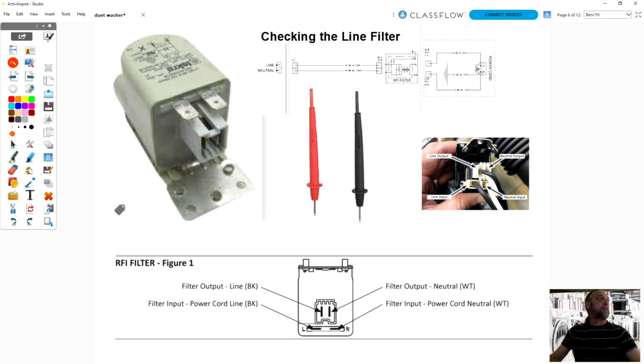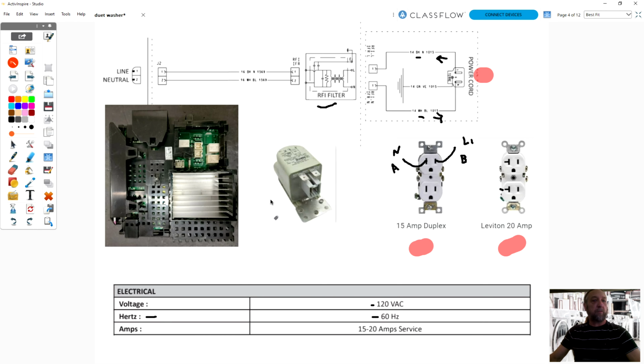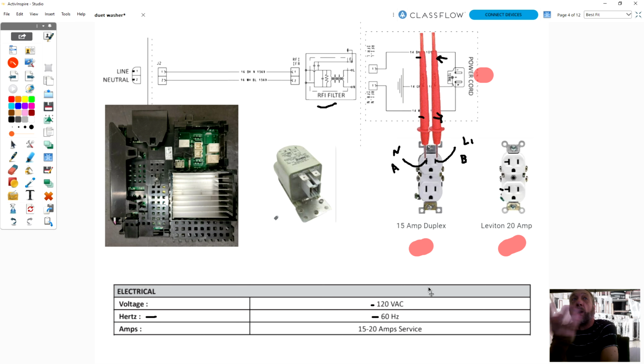Let me just copy this here. One second. So I use 2 red ones. It's faster than trying to bring a black and a red one over here. So if I put my meter leads in there, line 1 to neutral, that won't tell me if my polarity is right or wrong. It'll tell me if there's power, but not if it's wired backwards, where they put the black wire on neutral and the white wire on line 1, and that's these screws right here. The black wire should be attached to this screw and the white wire to this screw.